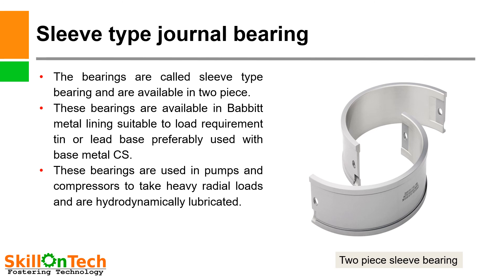Sleeve type journal bearing. You can see a picture of two pieces of a sleeve bearing. These sleeve type bearings are available in two pieces with babbitt metal lining — tin or lead base — suitable to load requirements, preferably used with base metal CS. They are used in large-size pumps and compressors to take heavy radial loads and are hydrodynamically lubricated. Other sleeve-type bearings suitable for radial and axial thrust loads will be discussed in an upcoming video.